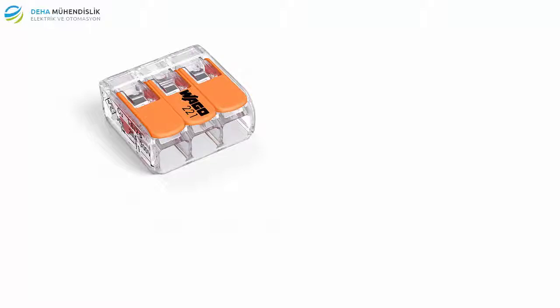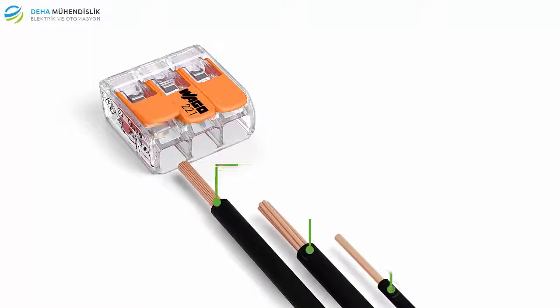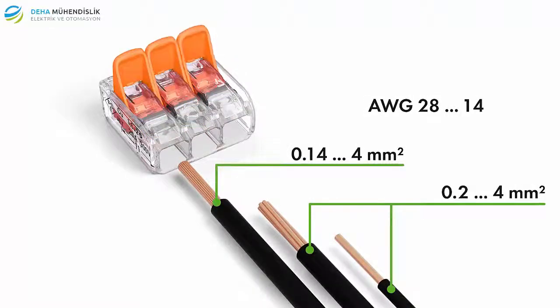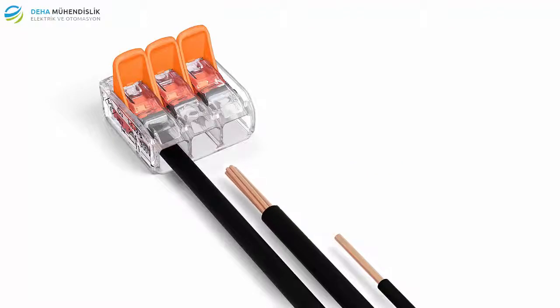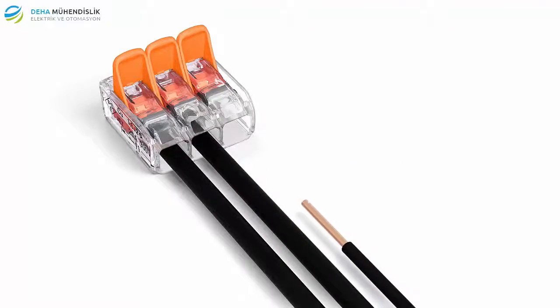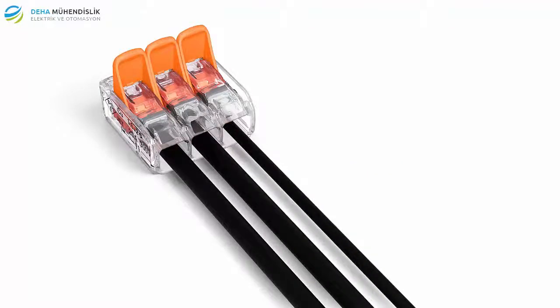The compact splicing connectors for all conductor types feature a large connection range, 0.14 to 4 square millimeters fine-stranded and 0.2 to 4 square millimeters solid and stranded 28 to 14 AWG. This flexibility permits a wide range of applications, especially when conductors of different types and different sizes are used together.